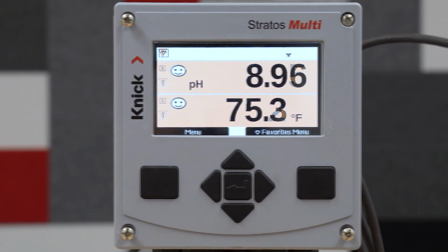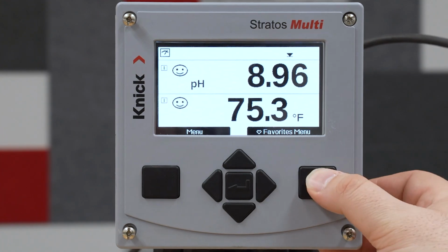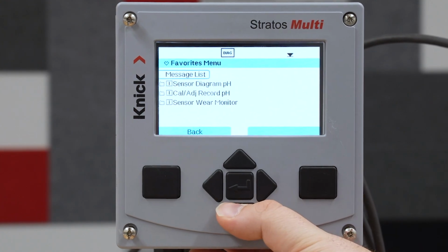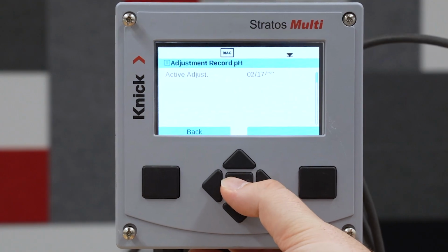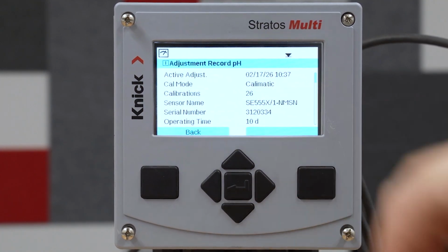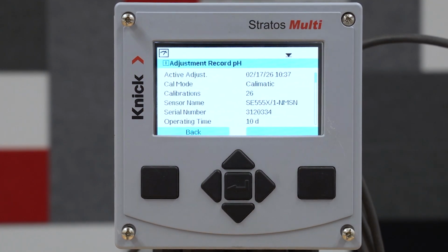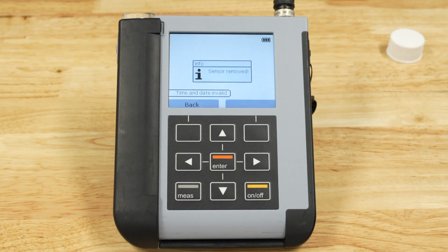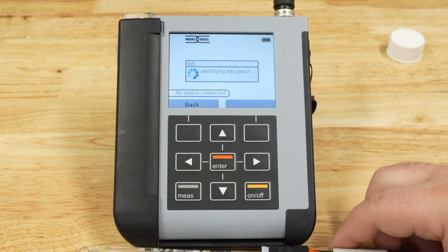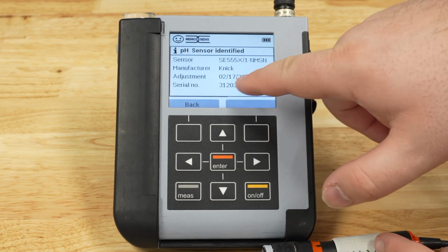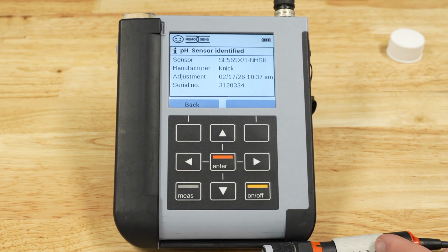What's nice about the Memosens sensors is that the calibration is stored locally on the sensor itself. So you can go and have the correct previous calibration pull up. We can go ahead and connect the sensor to another Memosens device, and it will have the correct adjustment from our calibration just a moment ago.